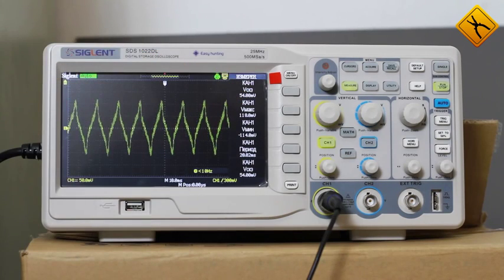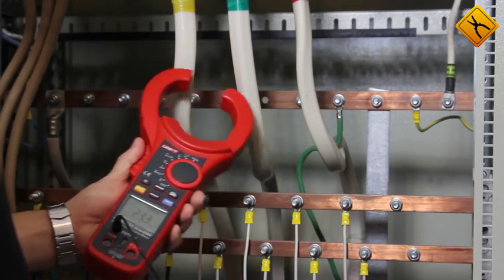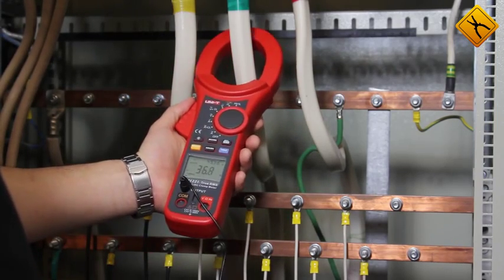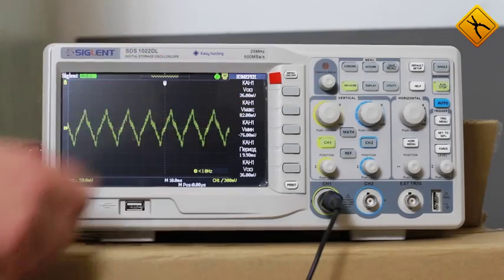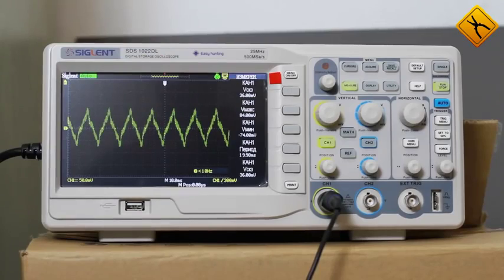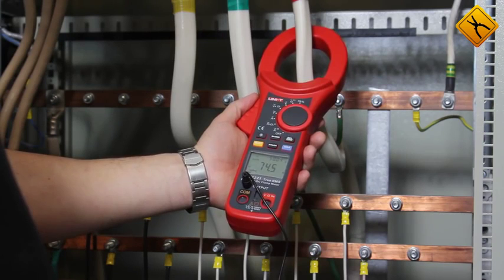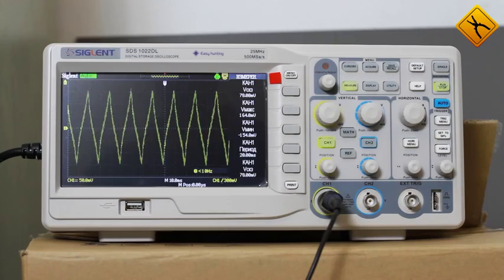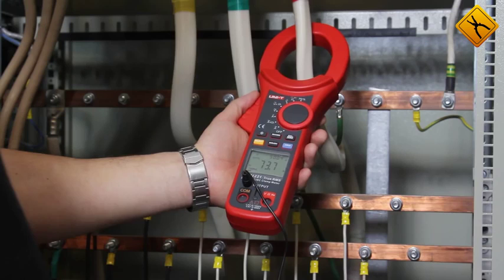The first conductor: 55 Ampere. Our voltage value is 54-55 millivolts. As we may see, the form is different from sine. Second conductor: 40 Ampere and the voltage value corresponds. Third conductor: 75-80 Ampere. As I mentioned, the form is far from sine.